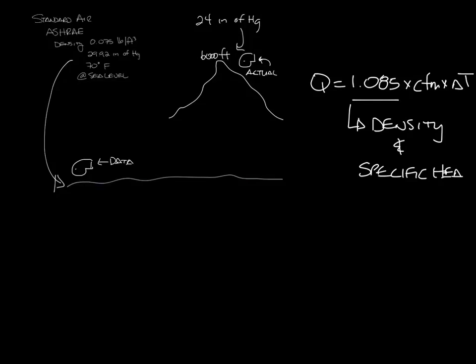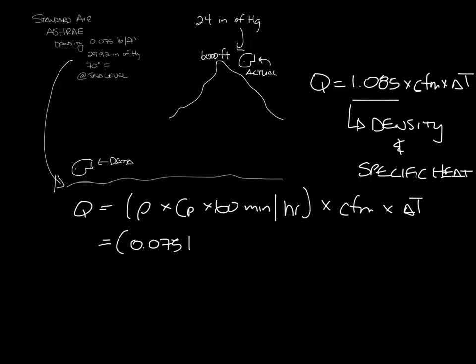So the load equation actually looks like this. Q equals the density times the specific heat times the conversion of minutes per hour, so 60 minutes per hour, times CFM times delta T. So for standard air, this equals 0.075 pounds per cubic feet times 0.241 BTU per pound per degree Fahrenheit times the 60 times CFM times delta T.